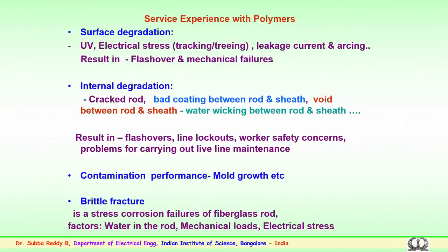During certain climatic conditions, or due to the area where the insulators are being used, with continuous fog or continuous mist on the insulators, there are reports of mold growth over a period of time, particularly in cold places or cold countries, or places where the temperature is much below freezing where these lines are being operated. So, there is contamination due to mold growth also. And as mentioned above, the brittle fracture, again I am stressing this.